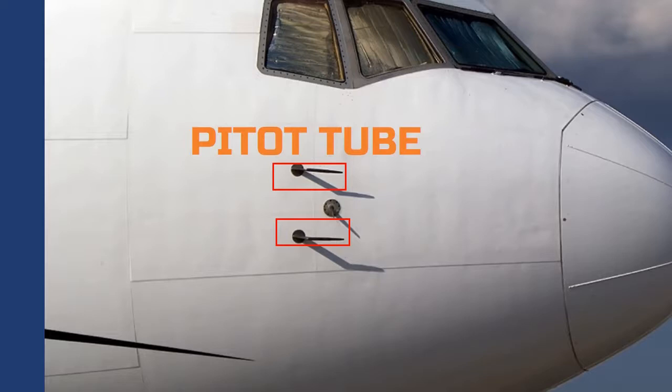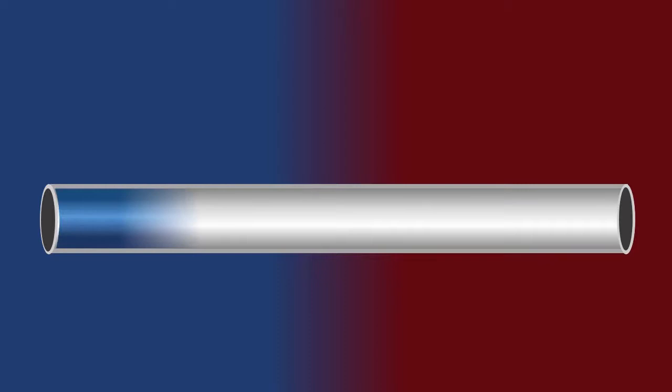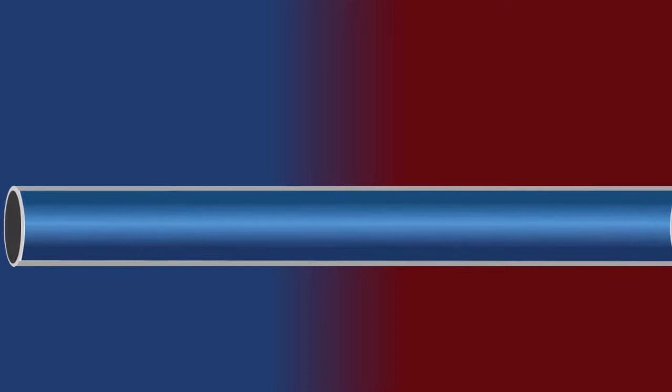Let's take a metallic pipe. Inside this pipe, some fluid is flowing. Pitot tube is used to measure the velocity of the fluid flowing inside the pipe. Let's understand its working principle. If we place a piezometric tube on a hole on the top of the pipe, we can measure the static pressure of the fluid by measuring the height to which the column of the fluid rises against gravity.